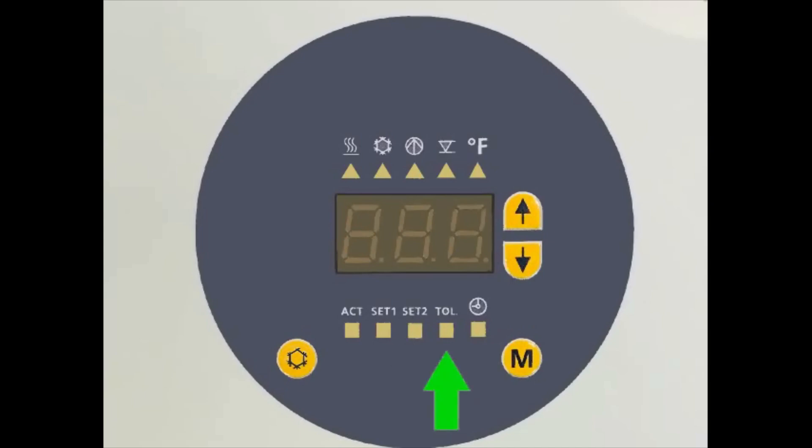Next, the TOL menu shows the tolerance values. This can be adjusted with the up and down arrow keys. Tolerance monitoring will begin once the tolerance window is reached or after the tolerance monitoring delay has expired. The default value for the delay is one hour.